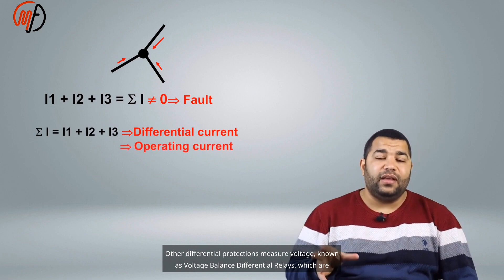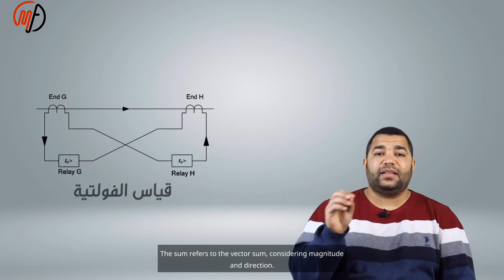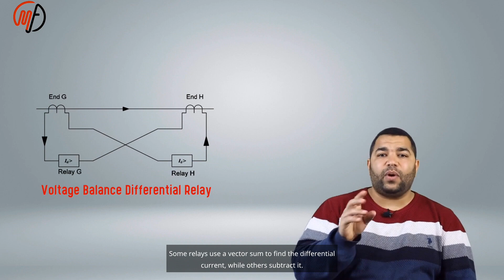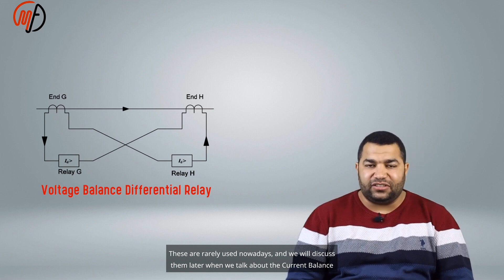Other differential protections measure voltage, known as voltage balanced differential relays, which are rarely used today. Normally, the sum of currents entering a point equals those leaving, so the differential current should be 0. The sum refers to the vector sum, considering magnitude and direction. Some relays use a vector sum to find the differential current, while others subtract it. These are rarely used nowadays, and we will discuss them later when we talk about the current balanced differential relay.